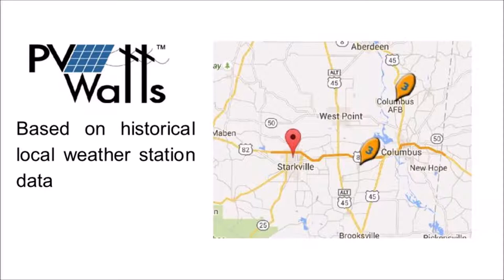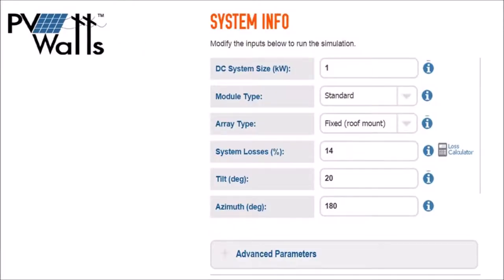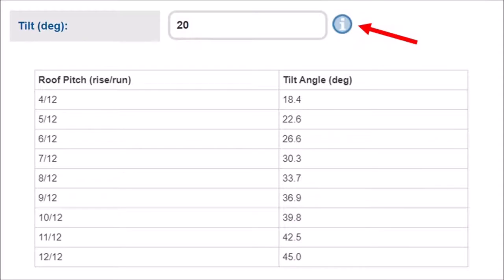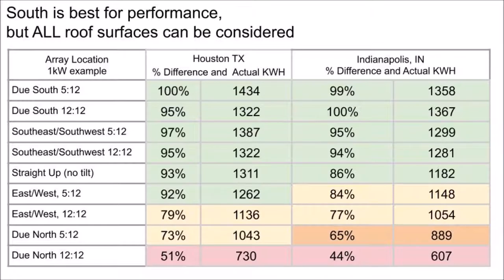Input your address and system size to get started. I recommend performing a PVWatts example using a 1 kW solar array size to keep things simple. A 1 kW solar array in Houston, Texas, facing due south at a 20-degree roof tilt angle will produce 1,400 kWh of energy per year. Summer days will produce more than winter days because the days are longer. A common 5/12 roof tilt is at a 22-degree tilt angle. The solar array is facing 180 degrees azimuth, which is due south. A 90-degree angle faces due east, and a 270-degree azimuth faces due west. All this can be modeled in PVWatts.